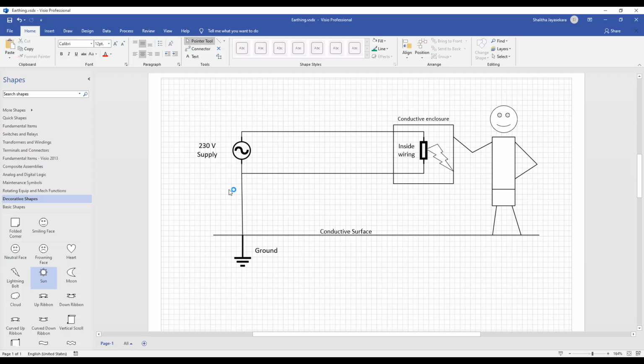So if this supply is isolated, this person will not get a shock. You should know this, because there's an earthing system where the supply is isolated. You will learn that system in this lecture. The person will not get a shock even if there's a fault inside your appliance. So it is a very special system, not recommended for use in domestic environments. We will see what the reason is. Okay, now let's say I am into... okay, do you guys know what the usual impedance of a human body is? Impedance means resistance. Okay, what is the usual human body resistance? Do you guys know the answer?